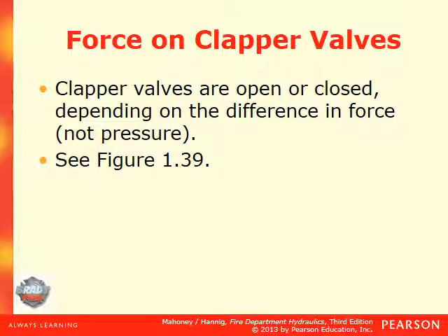Now remember, water always wants to be equal and spreading out, so to help keep it from spreading out, that's why you have that clapper valve in there. So you look on page 23, figure 1.39 gives you a good illustration of this. Clapper valves are open or closed depending on the difference in force, not pressure, force.